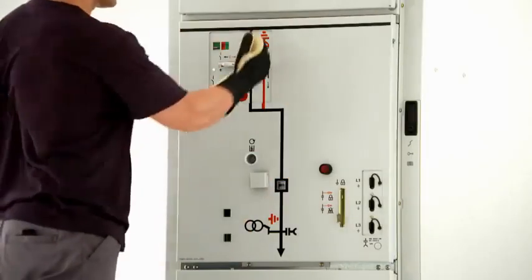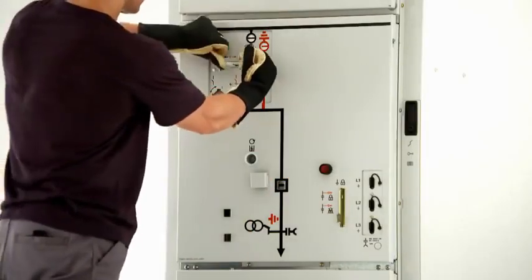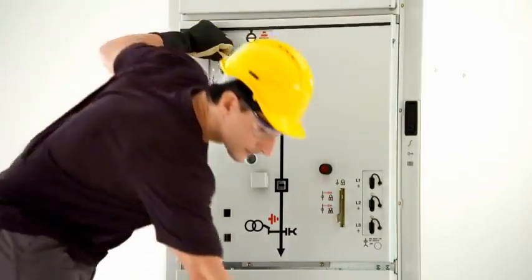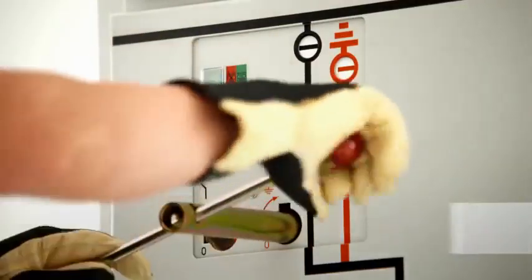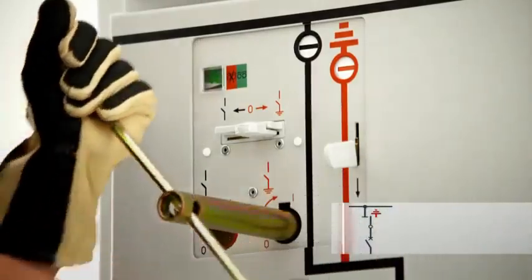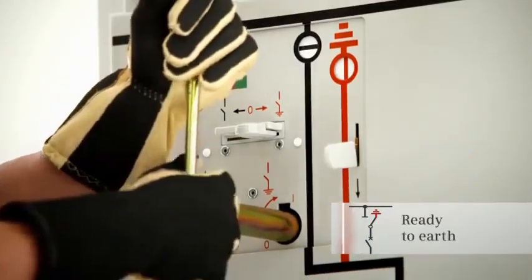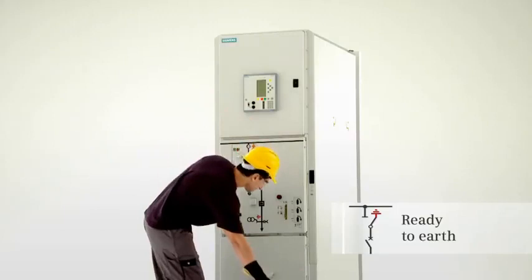The interrogation lever is now pushed down again and the control gate is pushed to the right to unlock the actuating opening for ready to earth. Turning the operating lever clockwise switches the three position disconnector to the ready to earth position.